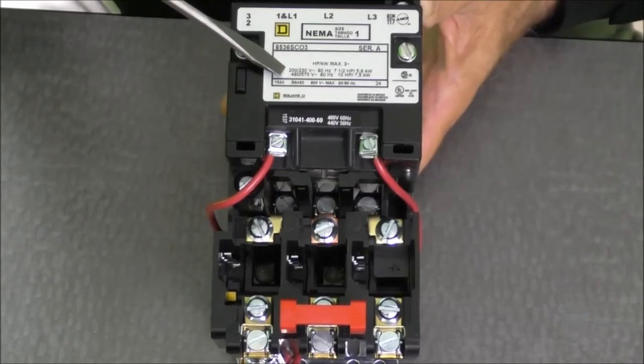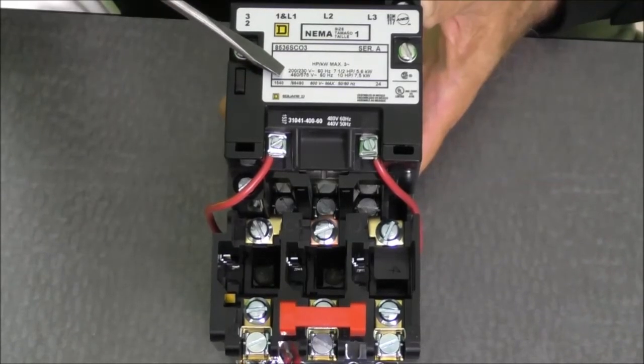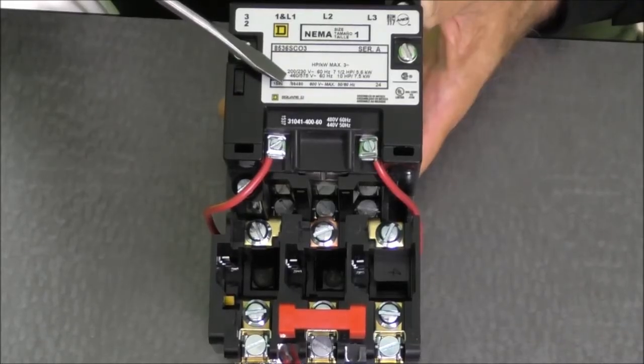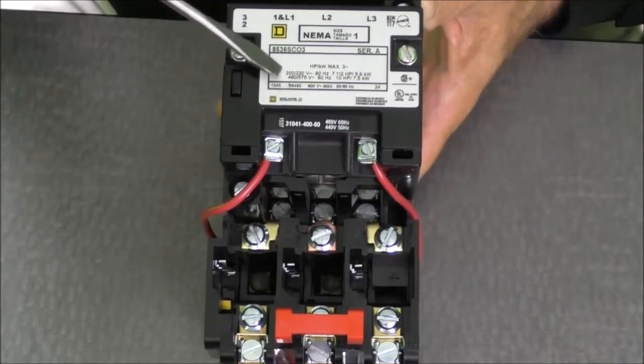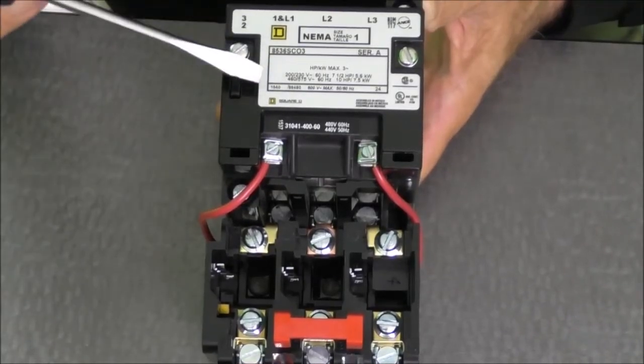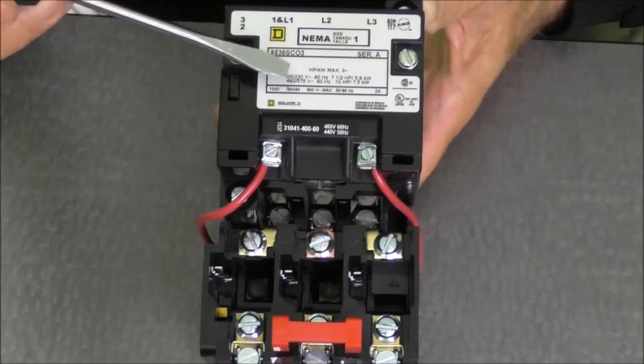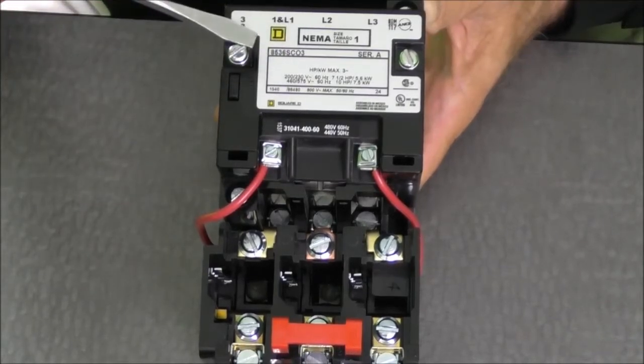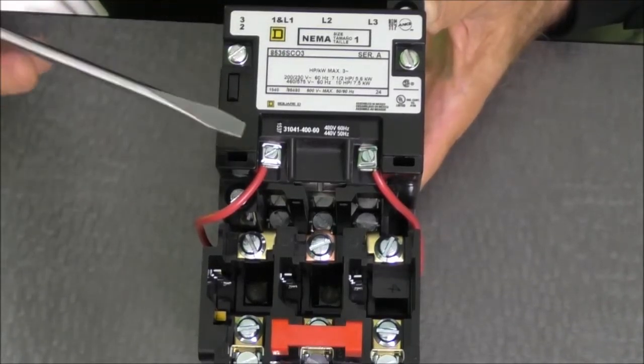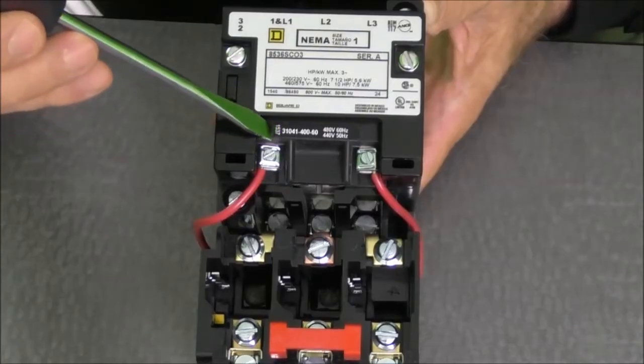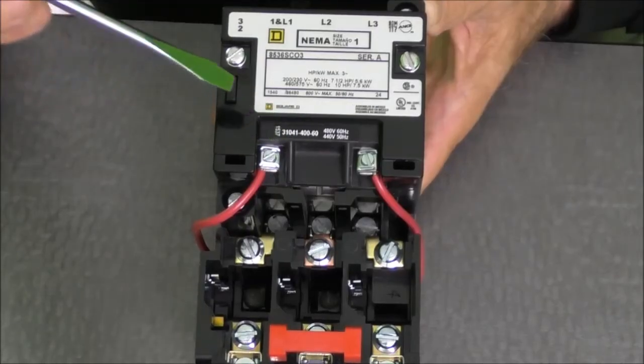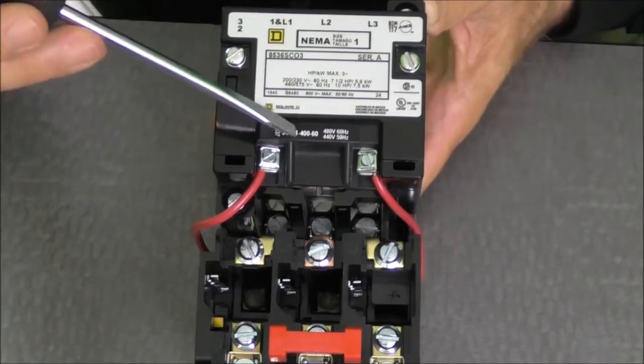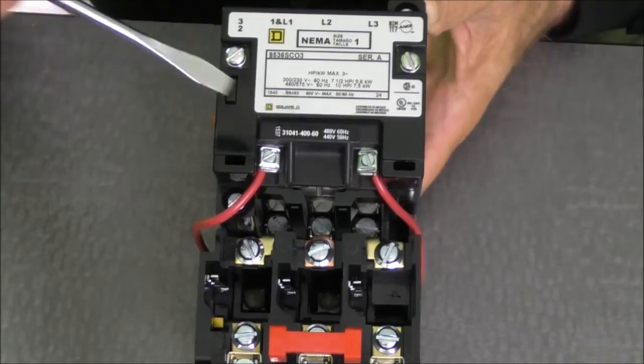Here we have our horsepower ratings. For 230 volt we have 7.5 horsepower. For 460 volt we have 10 horsepower. All NEMA rated size 1 starters will have exactly the same horsepower ratings. The interesting thing about this nameplate, there is no reference to a coil voltage. This particular starter has a 480 volt coil and we can see that by the label on the coil itself. It tells us that it's a 480 volt coil.